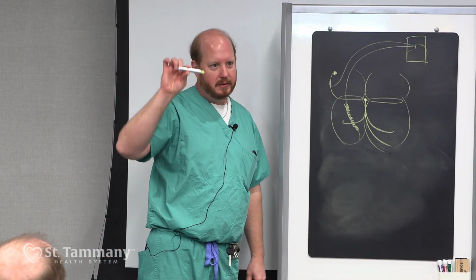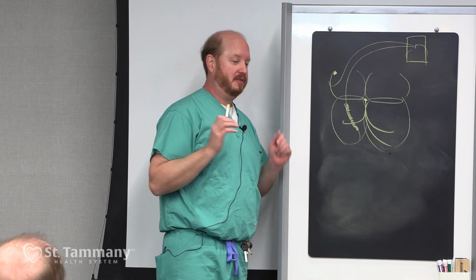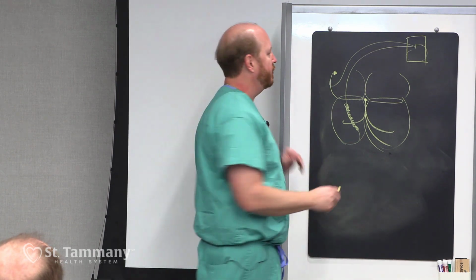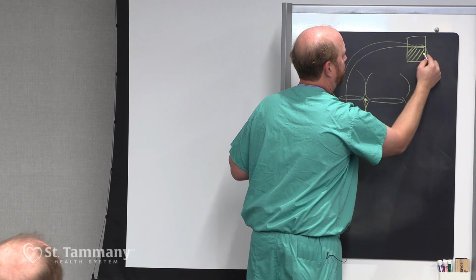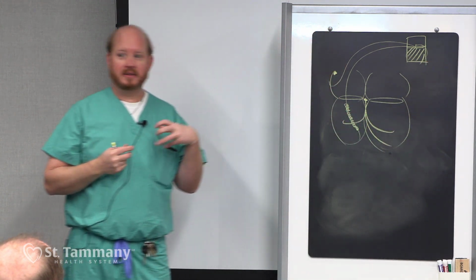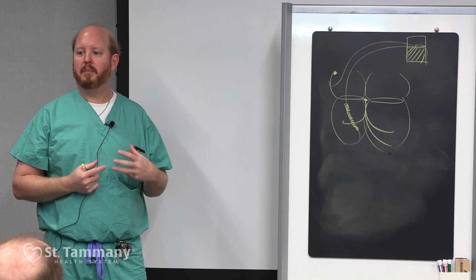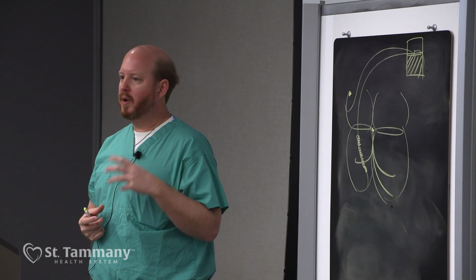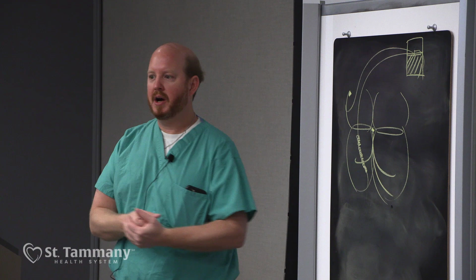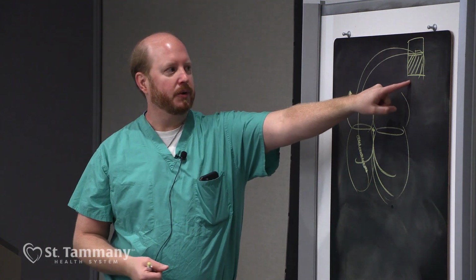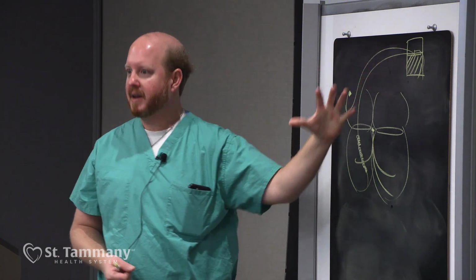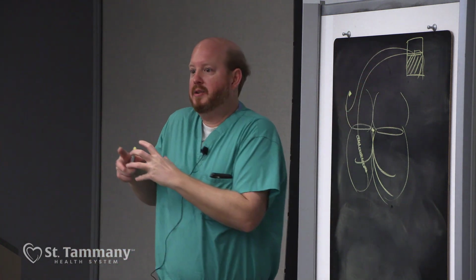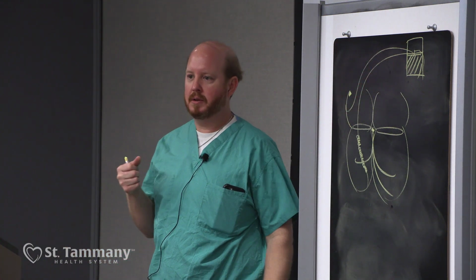And this is where it's just a little bit of extra knowledge. You're going to see through some stuff that you just never knew to even look at. Probably about 2/3 of this box, and why it's bigger, is something called a capacitor. When it's time to shock, this little device can load up its energy out of its battery, stack it up into this capacitor, hold it at high charge, and then deliver it suddenly.